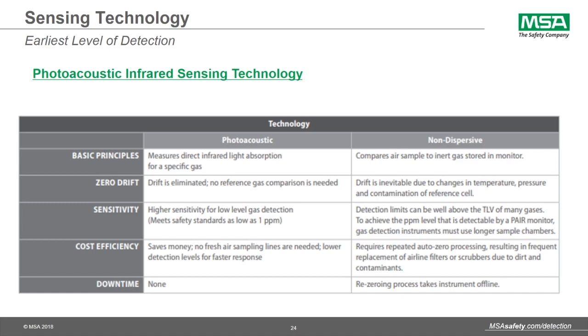In terms of sensitivity, photoacoustic has a higher sensitivity for low-level gas detection. That's how we're really able to get down to the 1 part per million. For non-dispersive infrared, detection limits can be well above the TLV for a lot of gases. And really to get to that low level, non-dispersive needs a long sample chamber in order to achieve that.